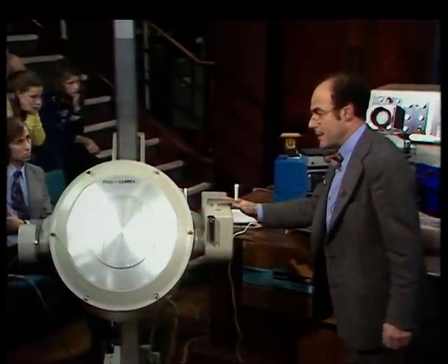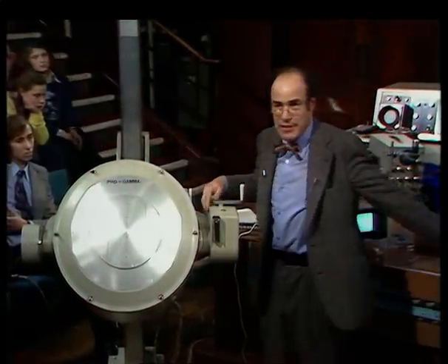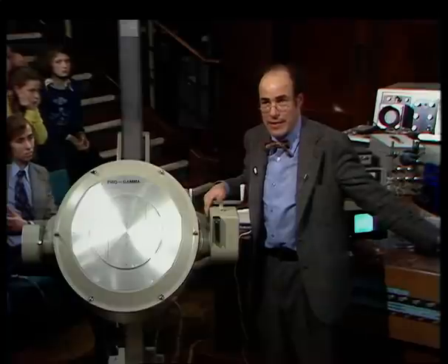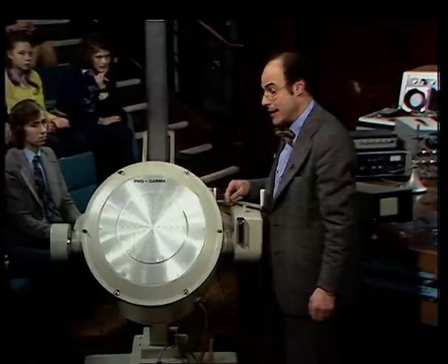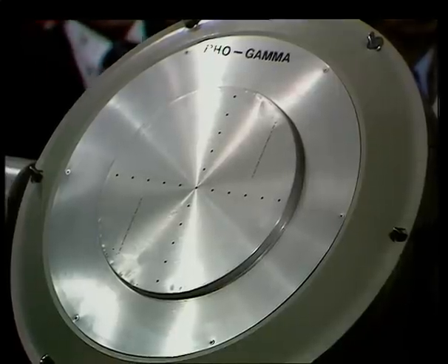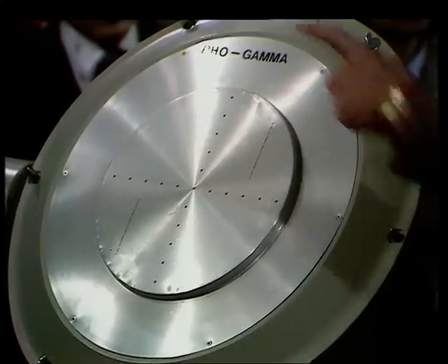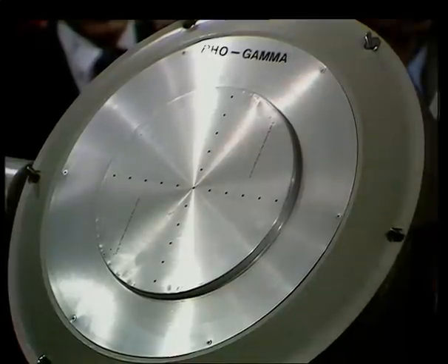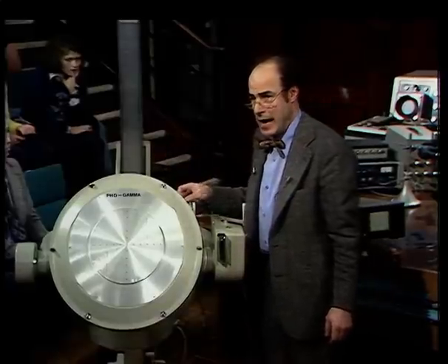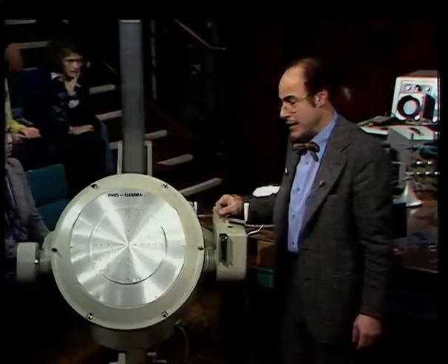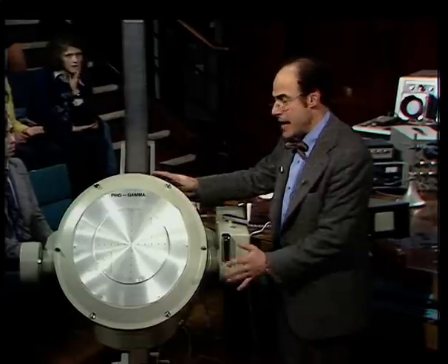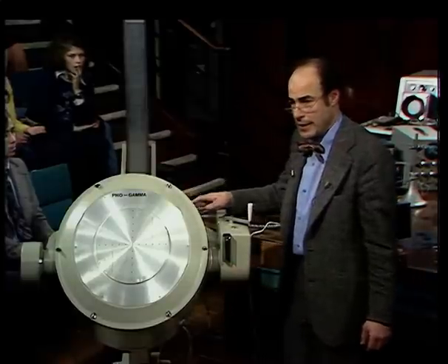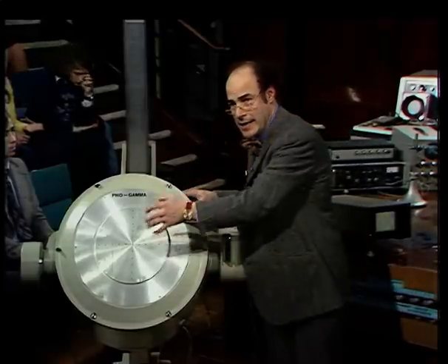This machine here is called a gamma camera, and it is constructed in just the way which I've shown you diagrammatically just now. Here is the active surface of it, and immediately behind this is a thick lead plate with 16,000 holes drilled into it, between 1 and 2 millimeters in diameter, which are the collimator, just like the collimator which the front row demonstrated just now. Behind that is the half-inch thick crystal of sodium iodide, and behind that are the 37 photomultipliers. And the whole thing is encased in a very thick lead casing, so as to avoid as far as possible rays getting into this from any direction other than the front.